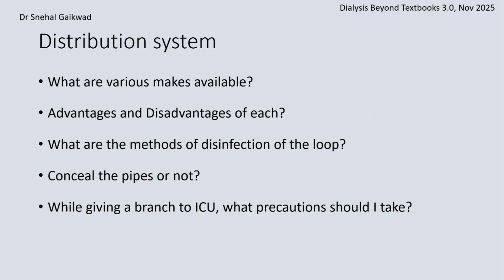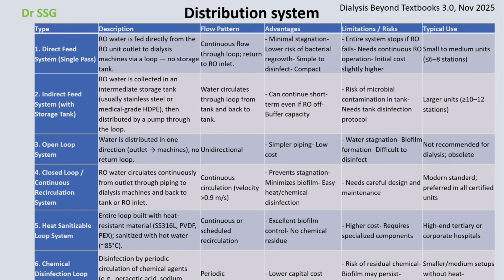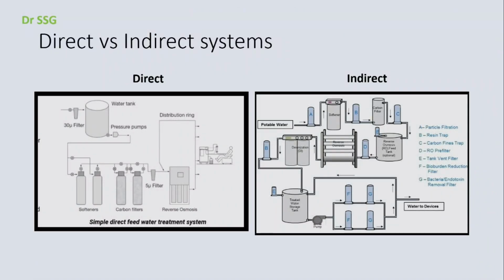So about the distribution system, what are various makes available, advantages and disadvantages of each? What are the methods of disinfection of the loop, and whether to conceal pipes or not? And if I want to set up my dialysis unit and ICU next door, how do I give a branch to the ICU? So there are different makes available, and it could be an open loop system or a closed loop system. Mostly it is a closed loop system in practice, wherein it could be a direct feed, that is the treated RO water is delivered to the dialysis machines and circulated in the loop. There is no RO holding tank. The indirect feed system incorporates a holding tank in the system, so it's a direct and an indirect.